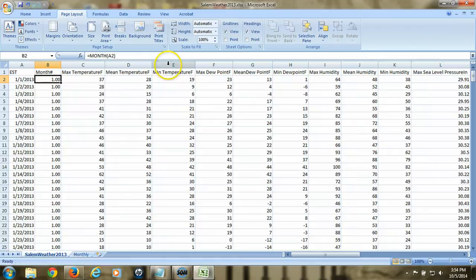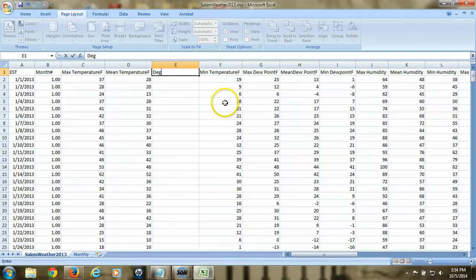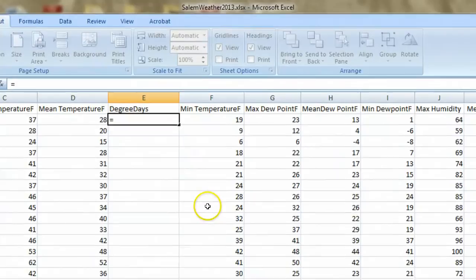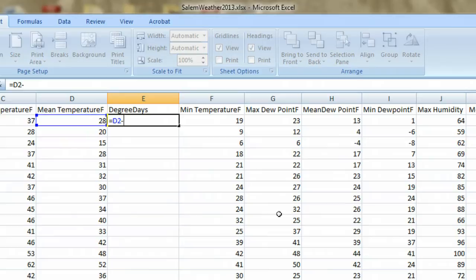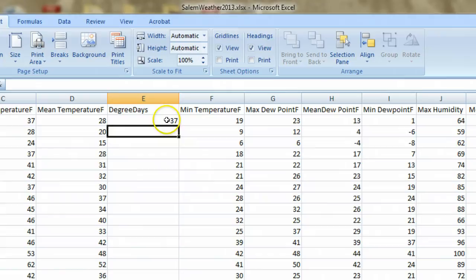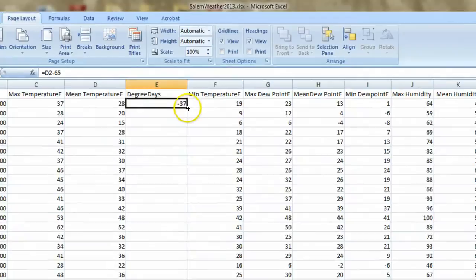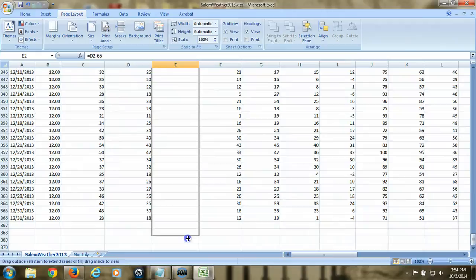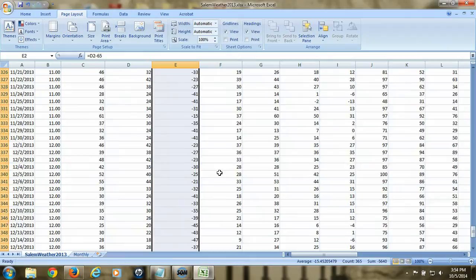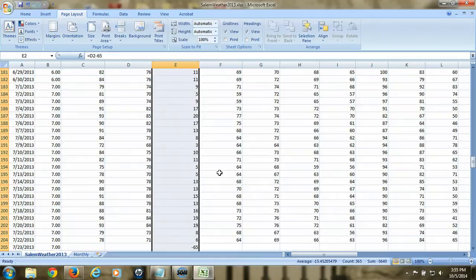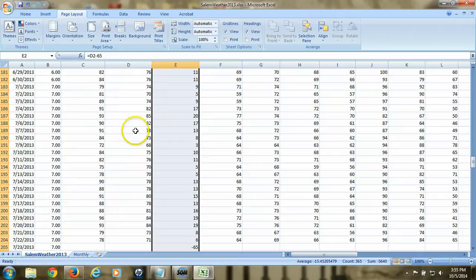I'm going to add a column right after the mean temperature column by right-clicking on the E column and choosing Insert. I'll call this column Degree Days, and in that column I'm going to take the mean temperature for a given day and subtract 65 from it. A negative number means the temperature was below 65, which implies a heating degree day. I'll copy that formula down the column by grabbing the little box in the lower right corner and pulling it all the way down to the last row. The negative numbers represent heating degree days, and positive numbers represent cooling degree days since those mean the daily mean was above 65.